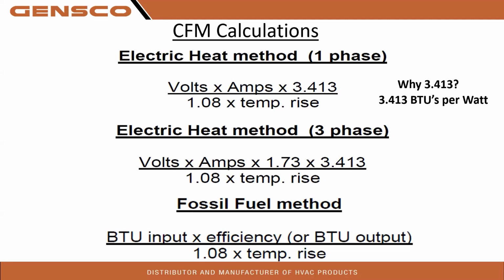Fossil fuel method, so you're using a gas furnace, you're going to use that BTU input times your efficiency. So if you're 96% or if you're 80%, 80% furnaces, you give me 80. If you're 90 plus, look at your tag or your BTU output. So on the data plate, it will list your BTU output.